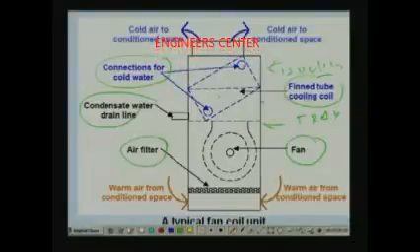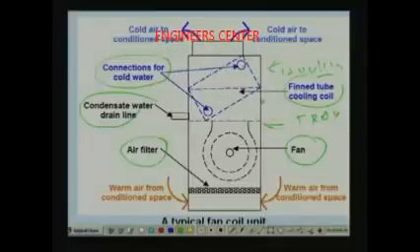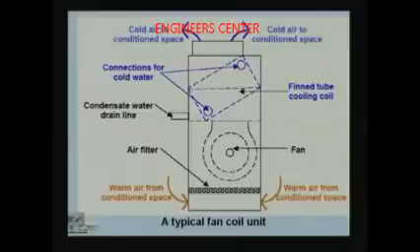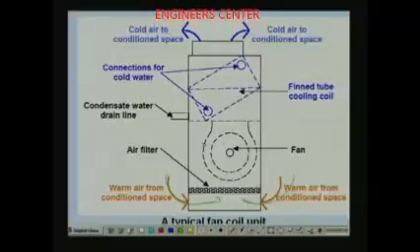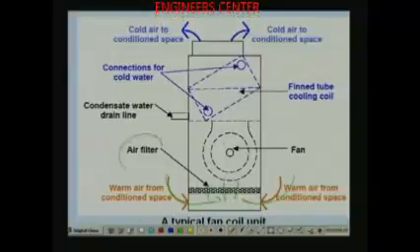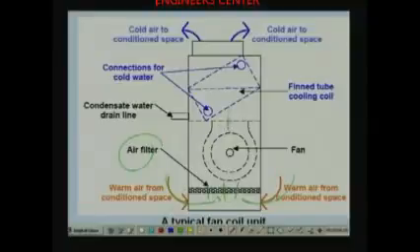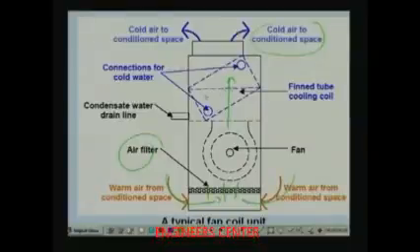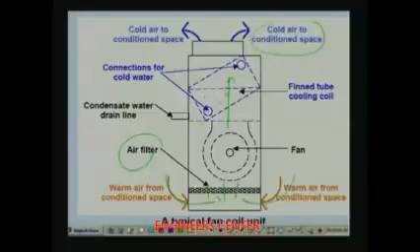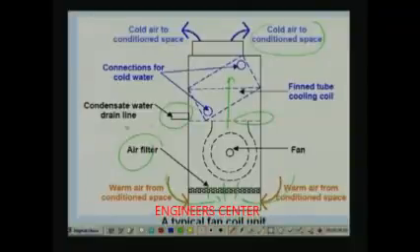As the name implies, the cooling coil is typically a fin-and-tube type. The fan draws warm air from the conditioned space into the fan coil unit. It is filtered as it flows through the air filter, and this filtered air flows over the cooling coil where it gets cooled and dehumidified. The cold air is then supplied to the conditioned space, taking care of the sensible and latent cooling loads. Since there may be latent load and condensation of water, a drain tray and drain line are provided for draining out the condensate water.